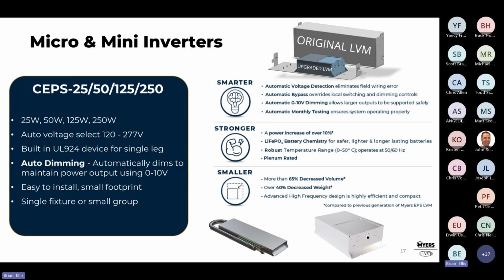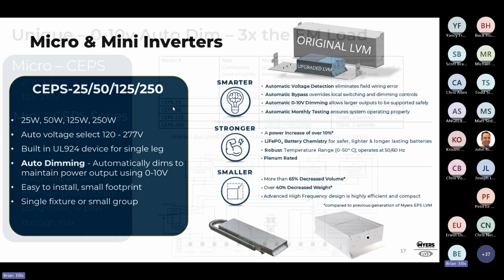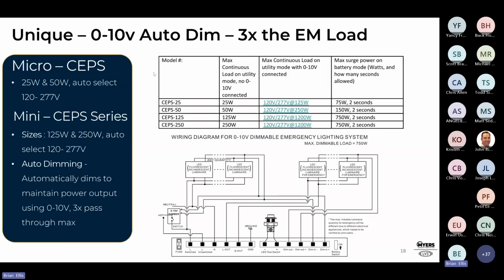As we talked about before, these micro and mini inverters are pretty unique. You can see they're very small in size, okay? They're 25 watt, 50 watt, 125, and 250, but they are your built-in UL924 device. They also have automatic dimming using 0 to 10 volt. How does that work? Basically the concept is, instead of being full light output, let's say I wanted to use this CEPS-250, right? And I wanted to do full light output. Well, you really wouldn't want to put a load of more than 210 watts on that inverter.